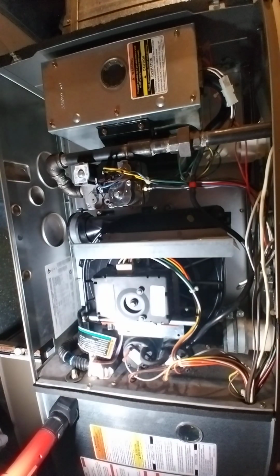Now, a lot of times it being full or clogged can be the cause of this problem, but in this particular case it was empty, and this is what caused the short cycling only in high heat mode. So let's rewind and find out why I found this and how I found this. About a couple weeks ago we had routine maintenance done where they just checked it over, changed the filter, made sure everything is good, and it was immediately after that it started doing this short cycling.